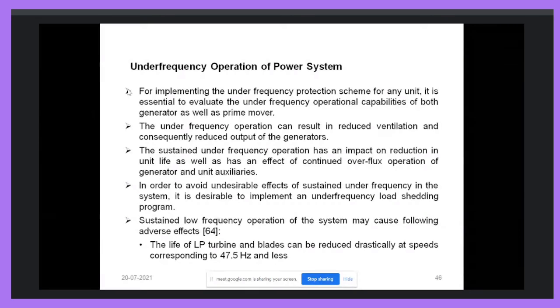Now actually the under frequency load shedding protection is designed to protect the system from under frequency operation. Because if the frequency of the system is low, then what will happen? It will affect the performance of the system. As we know, the output of the motors will reduce if the frequency is reduced. Okay, in case of the transformer, there may be a chance of saturation, because if the frequency reduces, then flux will increase. So when flux increases, the generator and motor may get saturated. Okay, so there is a limit of operation under the under frequency condition of the equipment. So we have to protect the equipment from under frequency operation.